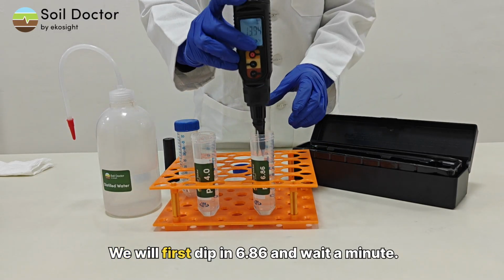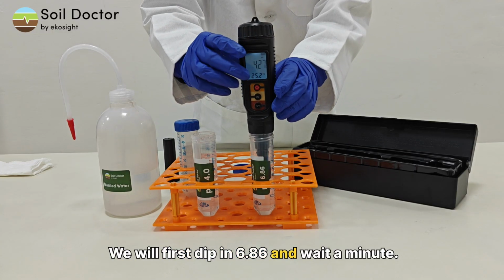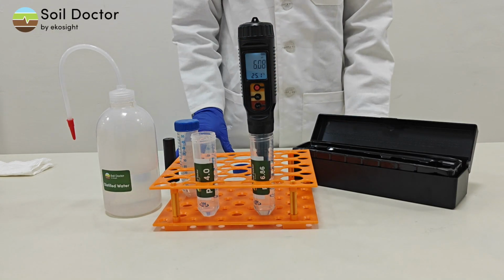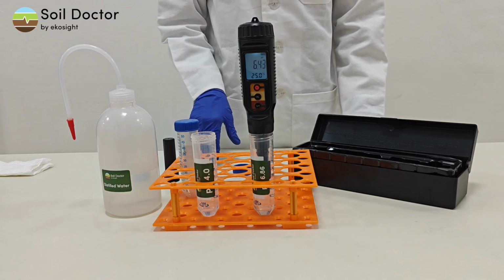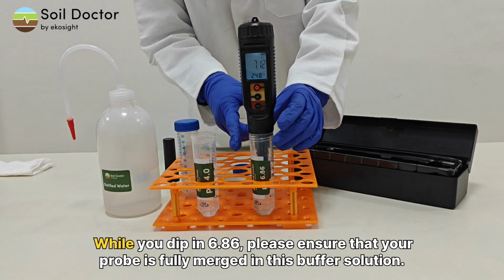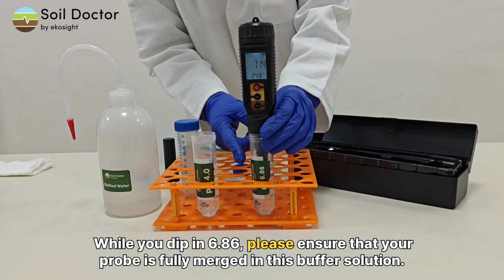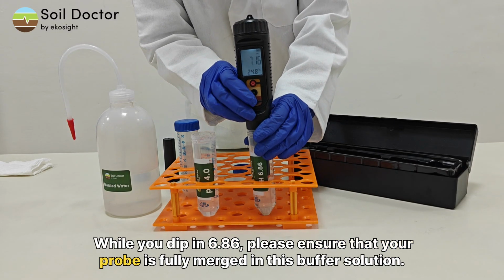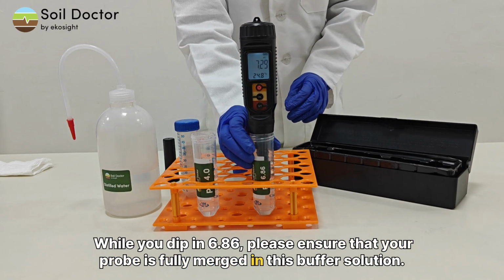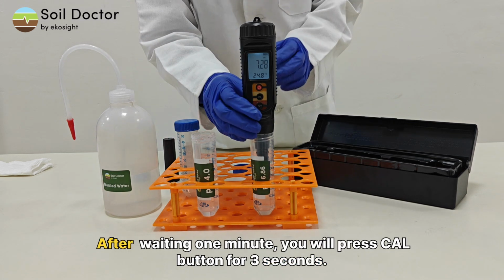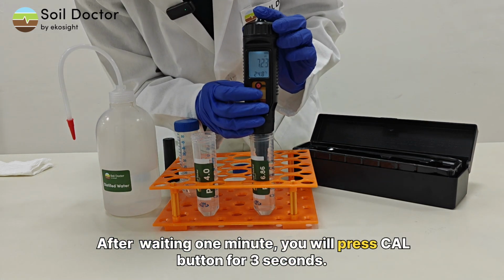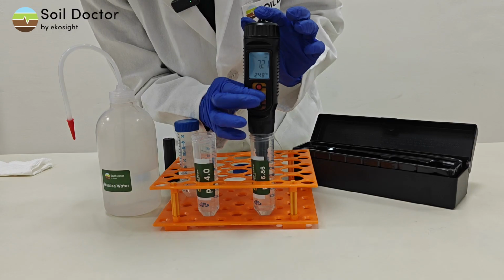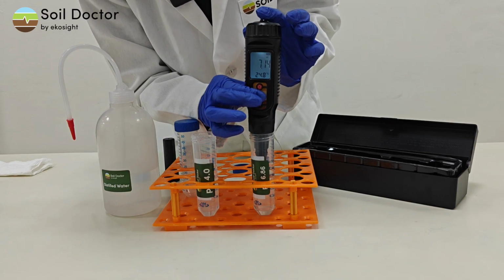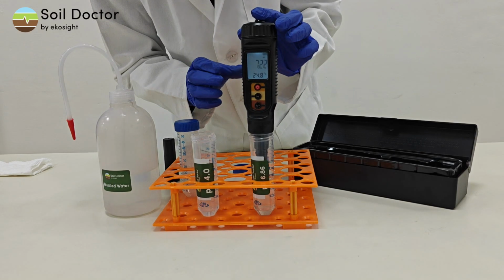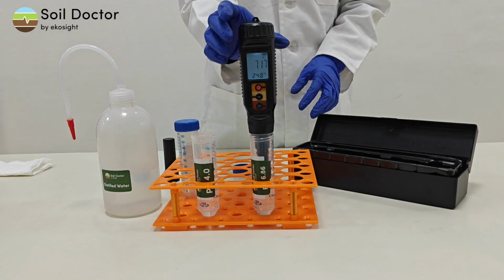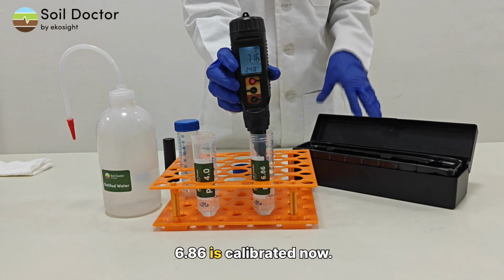We will first dip in 6.86 and wait a minute. While you dip in 6.86, please ensure that your probe is fully immersed in this buffer solution. After waiting 1 minute, you will press cal for 3 seconds. 6.86 is calibrated now.